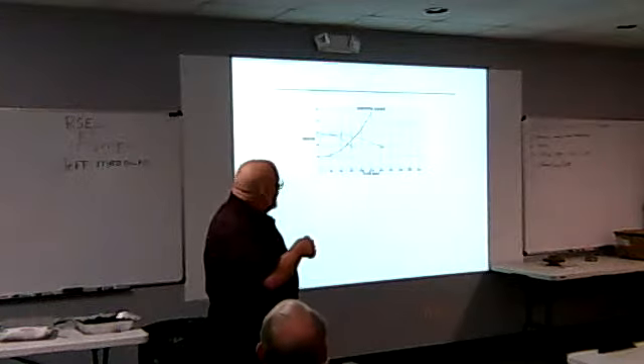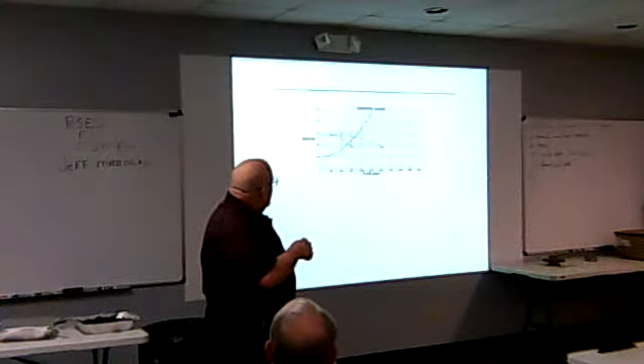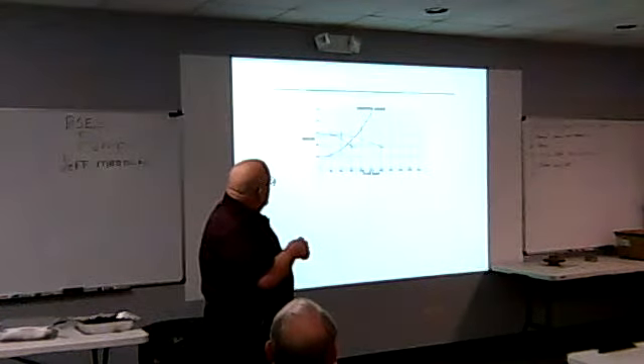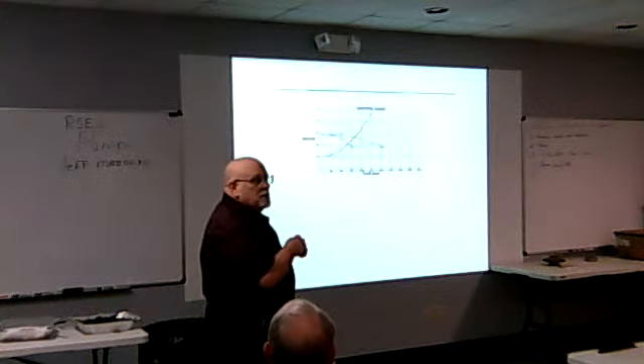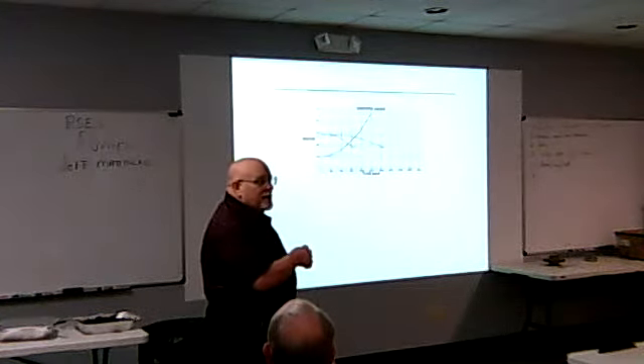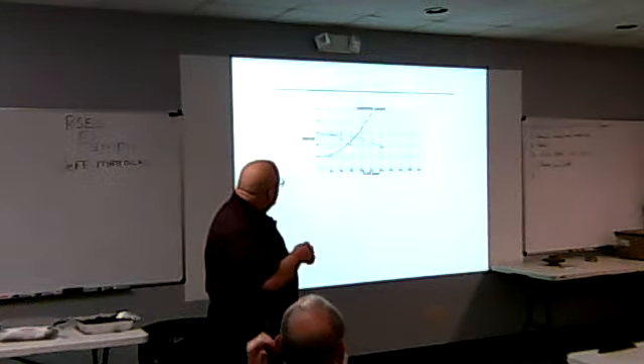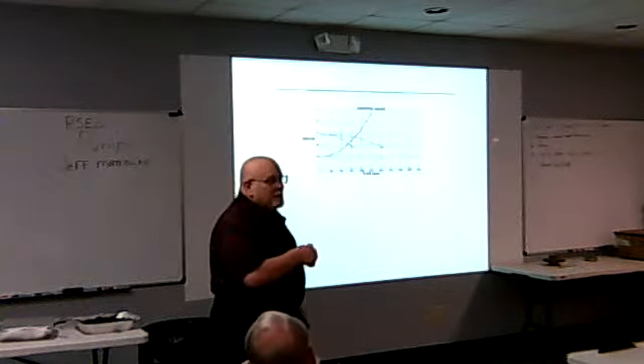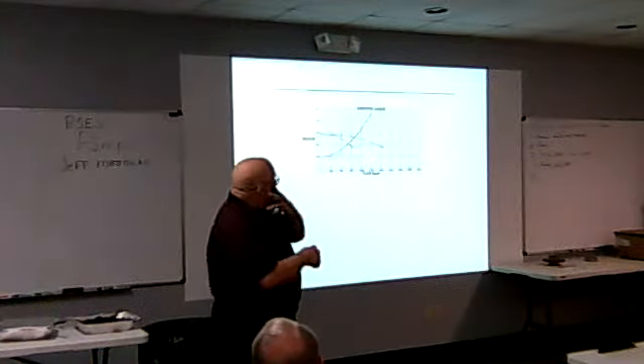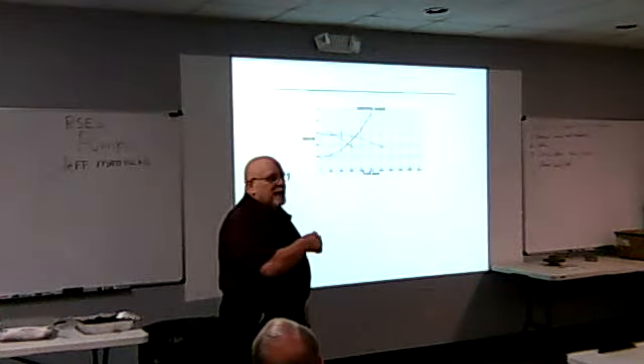But I'm limited about that head increase. What will happen though is when I go to 2 pumps from this point, whatever this point is, let's say it's 1,000, they'll split and share at 500 each. They'll each share what we're pumping. I can't come in here and say I want 1,800 GPM, put another pump in. No, I put another pump in, I just spent $4,000 for a new pump, and I gained 100 GPM.